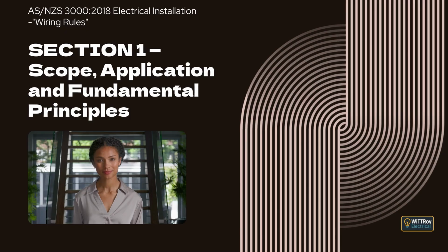Active, neutral, earth, protective earth, and equipotential bonding conductors must be shown correctly. Green or green and yellow are only for earthing and bonding conductors. Live conductors must not use green or green-yellow. Socket polarity must match the product specification and be consistent across the installation. Semi-enclosed rewirable fuses must not be installed. Condensation control must be considered where required.